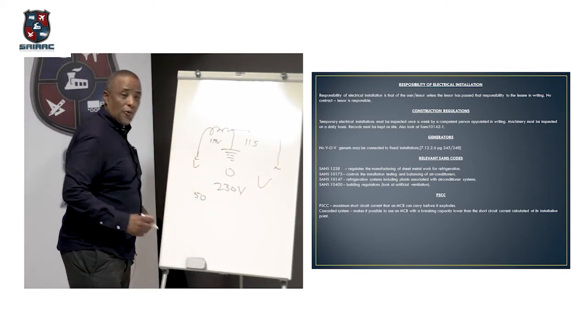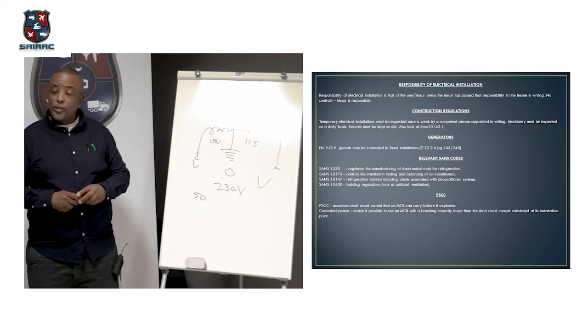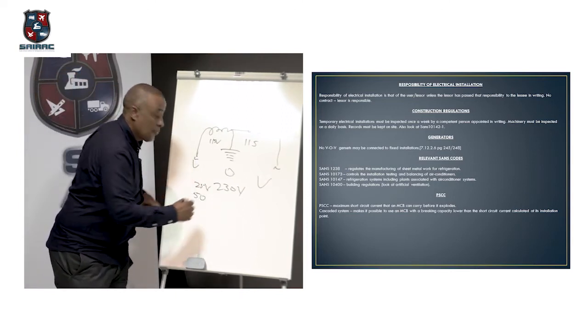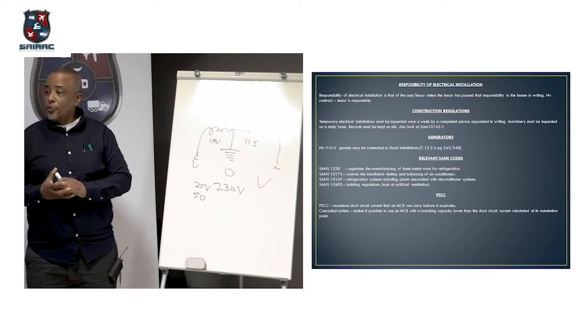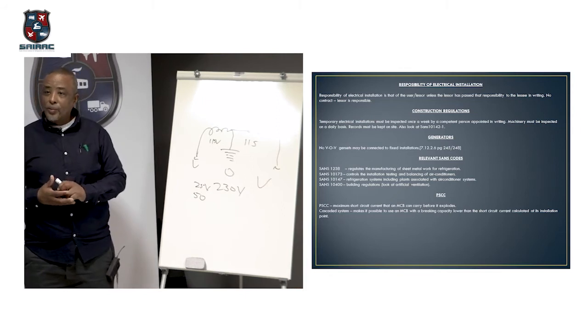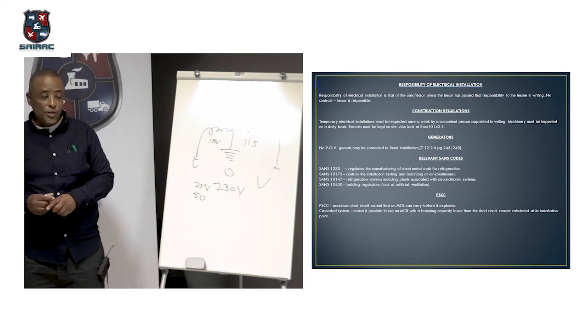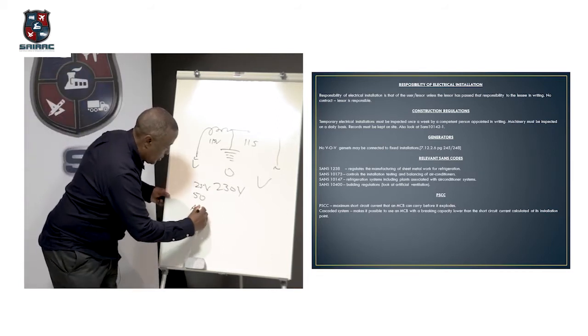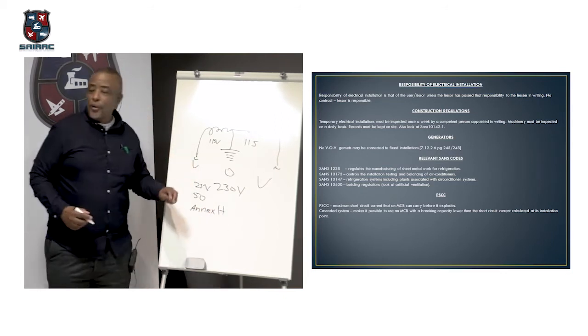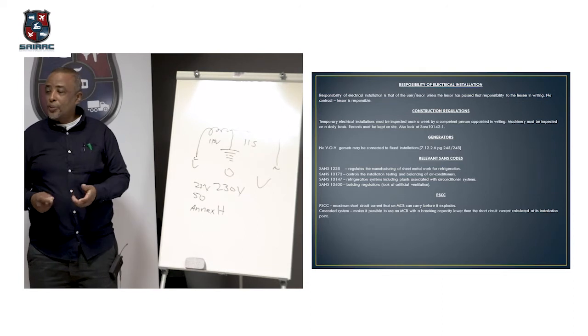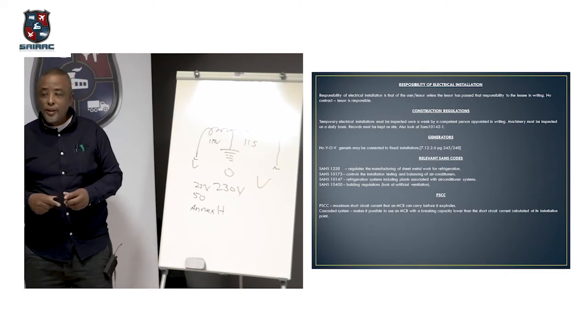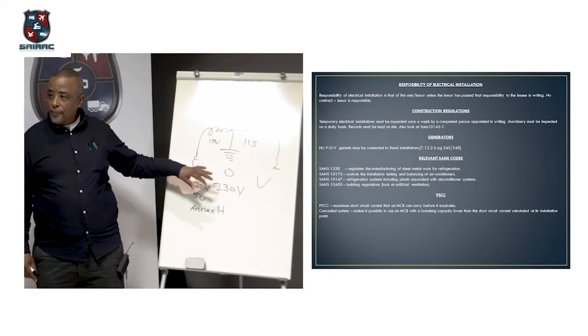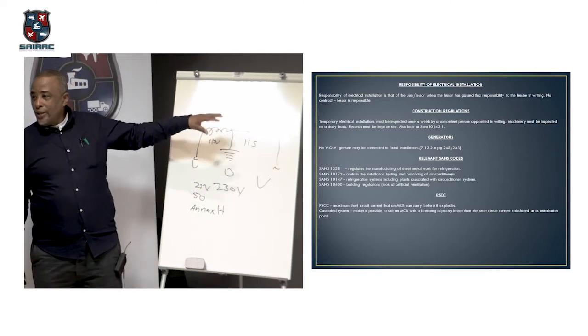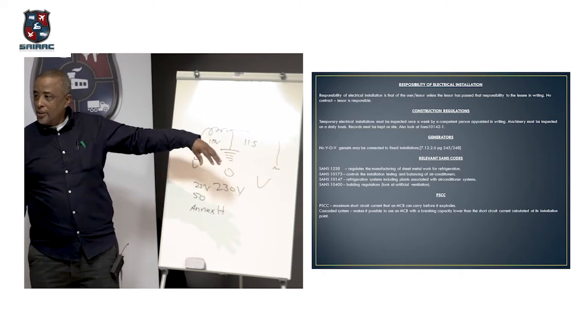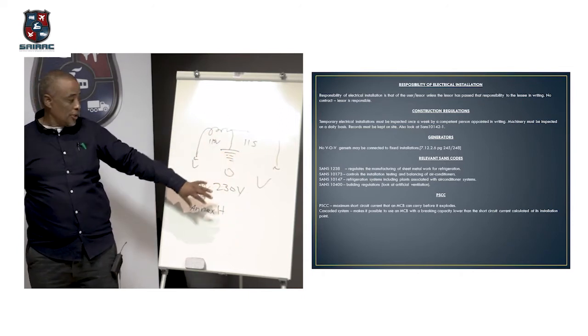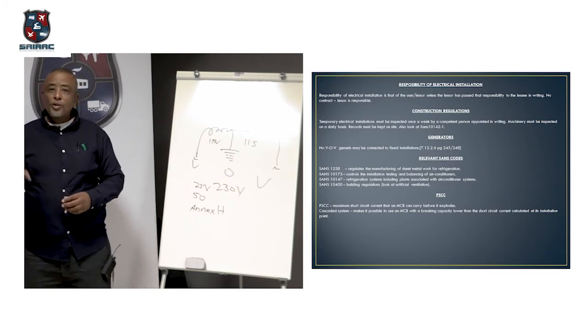If it's up to about 50 volts, if it's up to about 25 volts, you will notify the supplier, whether it's Eskom or the municipality, in the form of an Annex H. That's found in the regulation book. Okay, you don't have to be a registered person. You can get it on the internet. No, I haven't seen it on the internet, but it's in the regulation book, an Annex H. If you've got edition 1.8, it's there as an Annex K. Edition 2 is what we're working with now, so it's an Annex H. Okay, you fill that in, and then you notify the municipality.